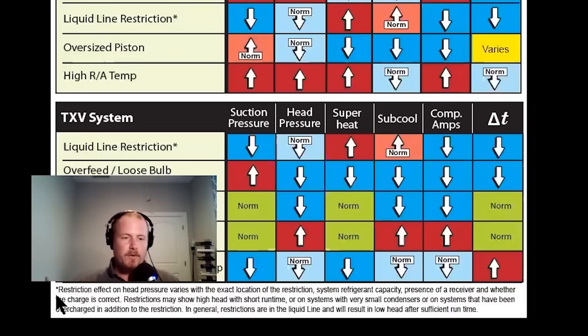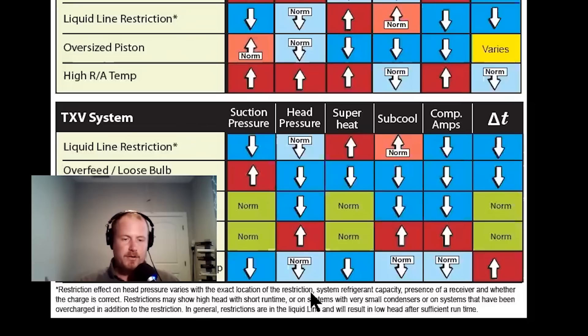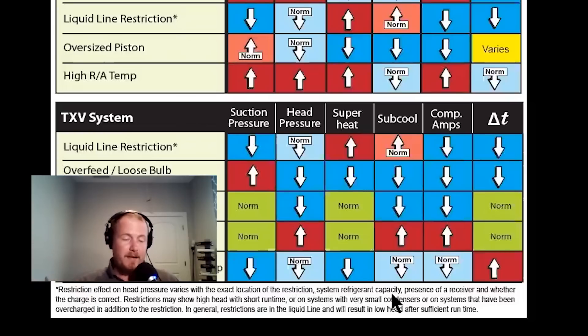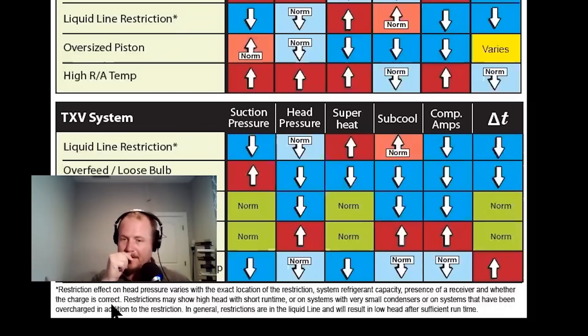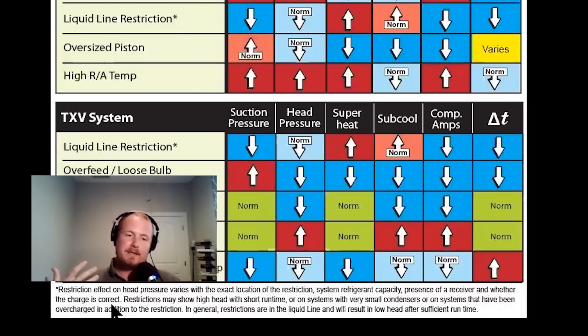Reading this note that goes along with the liquid line restriction: restriction effect on head pressure varies with the exact location of the restriction, especially if you have a receiver; system refrigerant capacity — meaning how much refrigerant the system can hold; presence of a receiver; and whether the charge is correct.